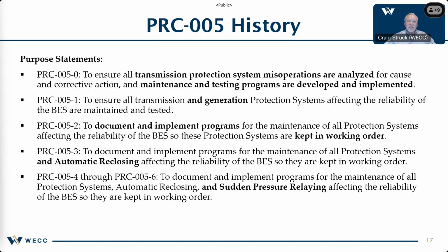In the second bullet, version 1 removed the verbiage around analyzing misoperations and added verbiage to include generation protection systems maintenance, to go along with the already included transmission protection systems maintenance. In the third bullet, version 2 added wording around documenting and implementing the maintenance programs. Moving on to version 3, that's where they added automatic reclosing. And finally, in the last bullet, version 4 added sudden pressure relaying.